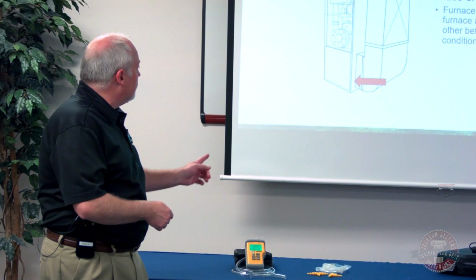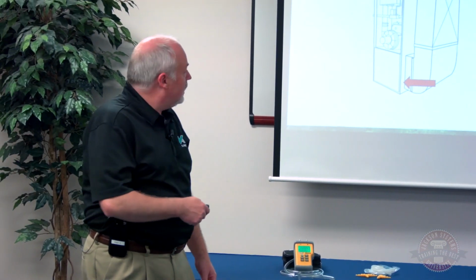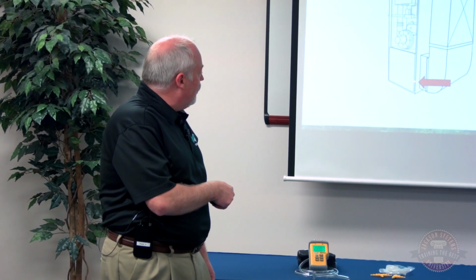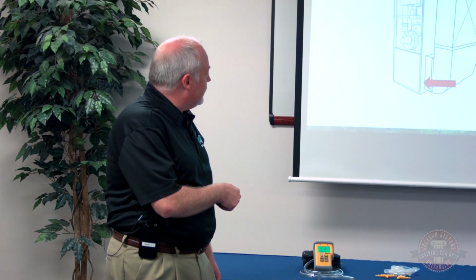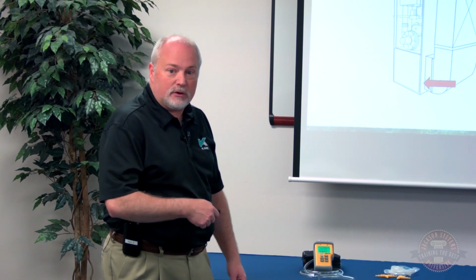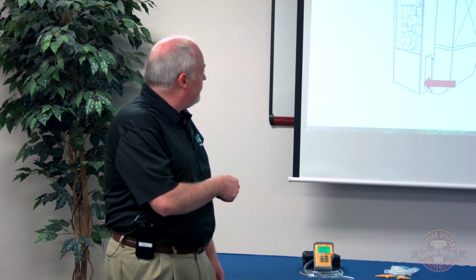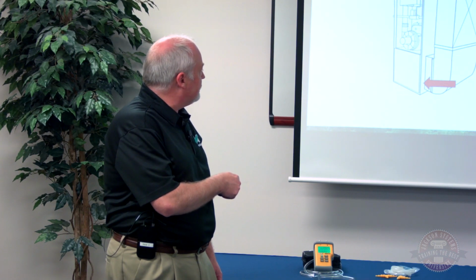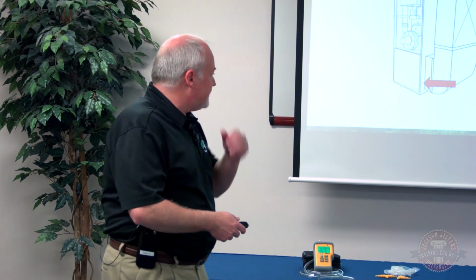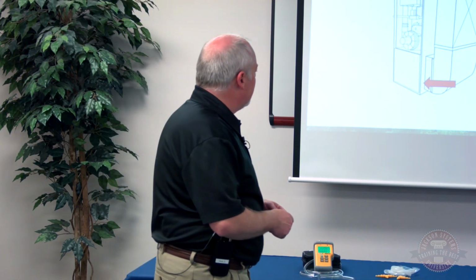All right, so on our gas furnace here, in this case, we're going to put one tip between our return air filter and our return side on our furnace. And then the other tip is going to go in between the furnace and our supply air coil, our air conditioning coil, because gas equipment typically does not ship with the A coil in the equipment. That's a separate piece. So we want to test it as that manufacturer designed and set up that piece of equipment. Okay?